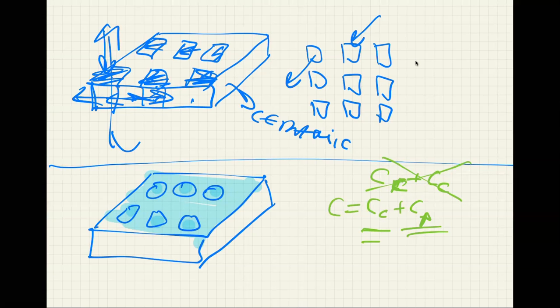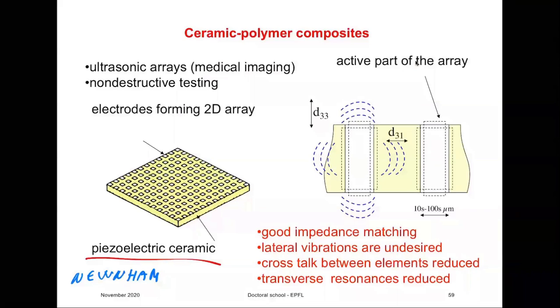I'm not sure if I'm forgetting something. Yes, by putting in polymer and using it as a single element transducer, you would also be reducing the density, and therefore you would be matching the impedance of such a composite with either water or a human body much better than if you have a monolithic ceramic piece. And so here it is. So you are getting good impedance matching, both electrical and acoustic.